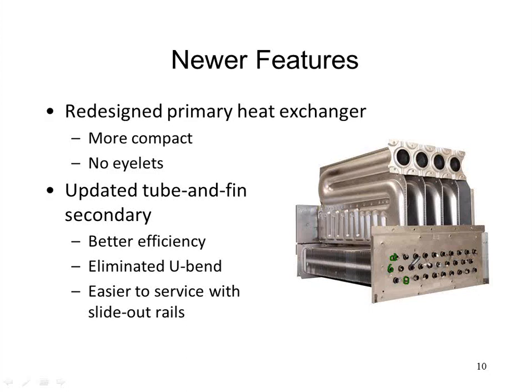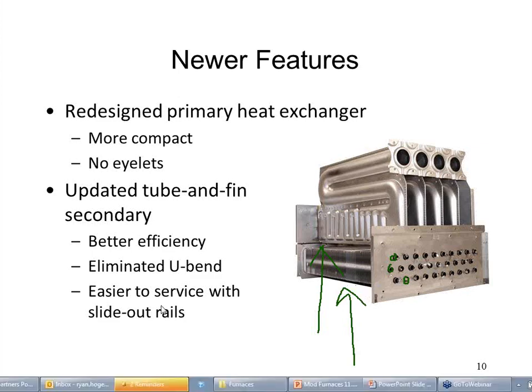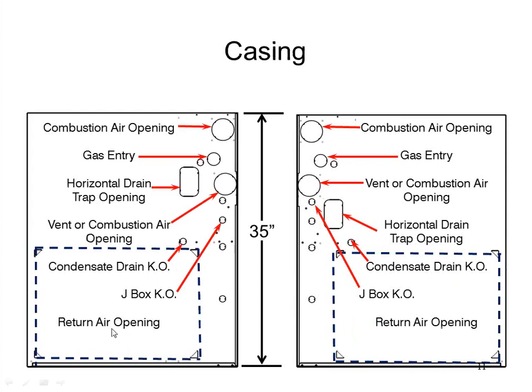So on the positive side, there's quite a bit of things that are going on here to increase efficiency. On the negative side, if you're used to old Carrier and Bryant furnaces, this one does have tighter airflow paths on this side of the air exchange. So cleaning could be a little bit more important, or filter changes can be more important depending on which way you look at it. Change the filters more regularly, or wait for them to get filthy and then have to clean the unit. So the positive is efficiency, the negative is a little bit more maintenance, but stuff they should have been doing anyway.